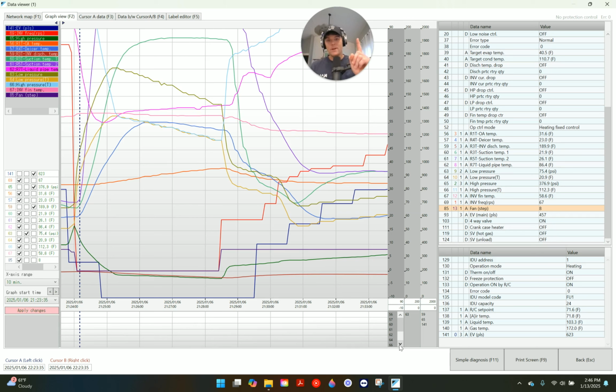There's the compressor, right? So we talk discharge temp, compressor speed, then there's head pressure. That's right after that. That's where the sensor's at. What is my saturation temperature? What is my head pressure? Okay, move further. Where is it going? Is it going outside? Is it going inside? It's going inside. Okay, heat exchanger pulses, temperature, in, out. Okay, and I follow that.